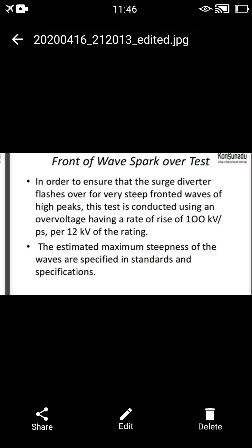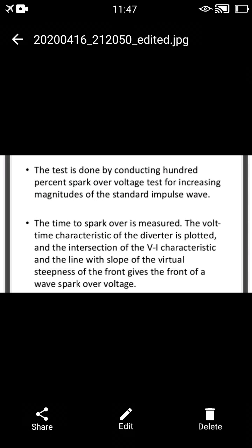That test is called the front of wave spark over test. In order to ensure that the surge diverter flashes over on very steep front waves of high peaks, this test is conducted using an over voltage having a rate of rise of 100 kV per microsecond per 12 kV of the rating. So this is the test in which the front waves are used for the spark over test. The estimated maximum steepness of the waves is specified in the standard and specification.